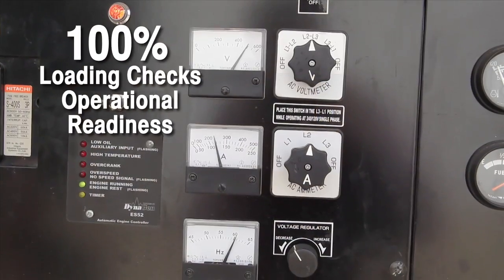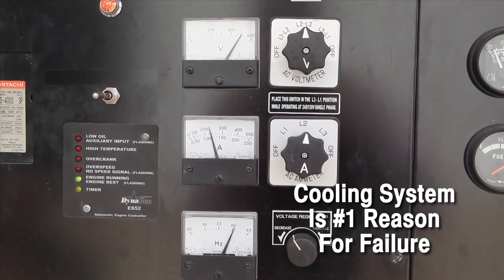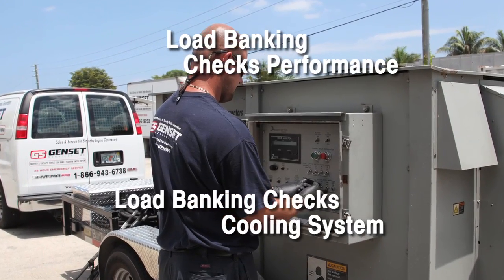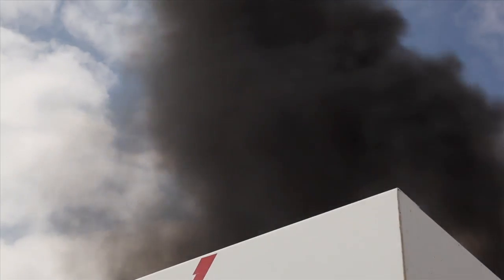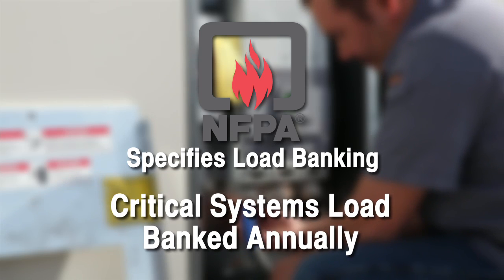capacity. Testing to 100% of capacity ensures the cooling system, the most frequent reason for failure, is working efficiently. Only a load bank test can load the system to full capacity and attain the temperatures to test the cooling system and burn off harmful excess fuel and carbon deposits. The National Fire Protection Agency recommends annual load bank testing of critical load generator set installations.